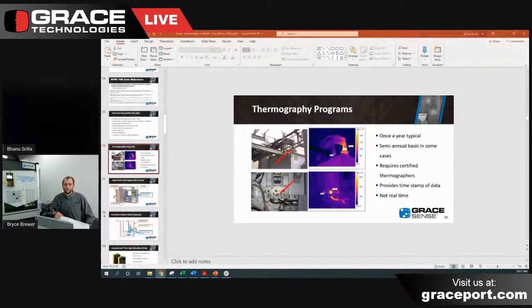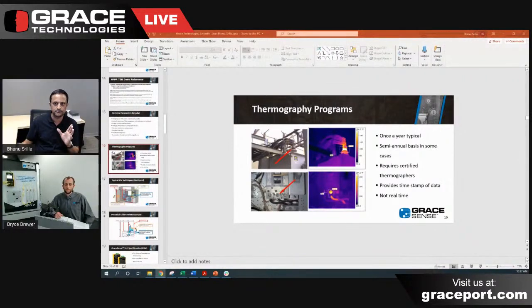Last but not least, whenever you make these thermography programs and try to do anomaly checks, all you're getting is the timestamp. You're getting temperature data for that specific point in time. You're not getting what's going on two months before, or what's going to happen six months down the line. You can only say what's happening at that given point in time with that predetermined load criteria.